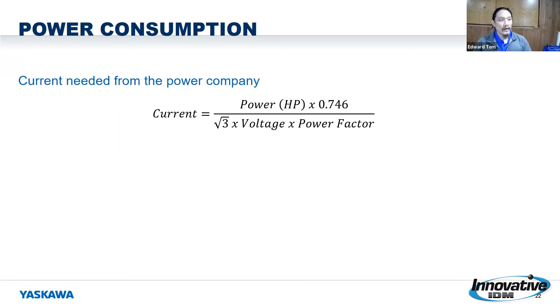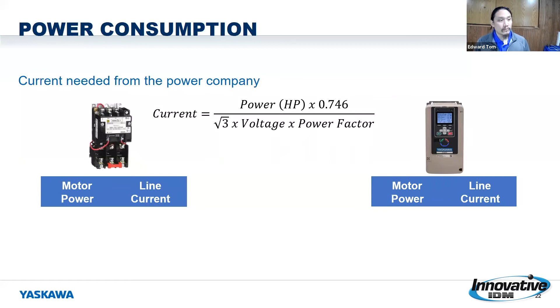Now, I wanted to look at something a little bit differently too. So that's power factor. But now I also want to look at the current, because the current that we talked about earlier is also going to affect the amount of losses that you have in your system, how much you're drawing from there. Now, I'm going to assume that you're running a motor across the line. So you've got an across the line starter, and we're going to compare it to a drive. And I'm going to use a 100 horsepower motor as my example.